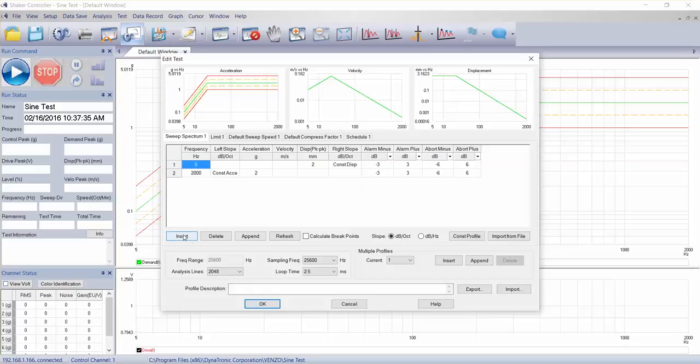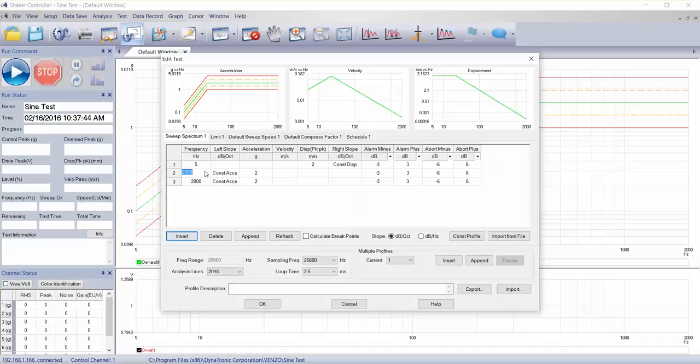That's based on what's entered here as the default break points for the sine sweep test. We can insert additional break points. So let's say I want a point in between 5 hertz and 2000 hertz. I can simply key that in.